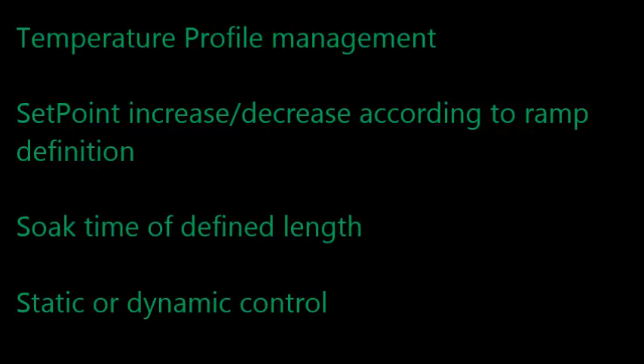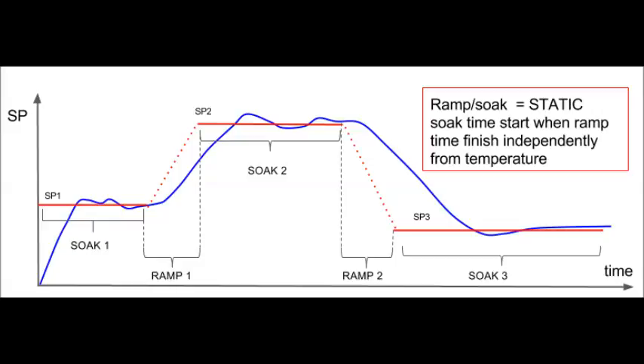Through this feature you can define and manage a full temperature profile. Instead of setting just a single setpoint and changing it manually, you can move your setpoint from one value to another and increase or decrease temperature according to a ramp definition. You can also keep your temperature stable for a defined length in the soak period.